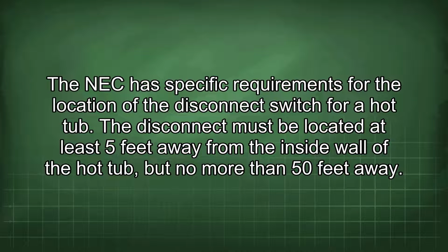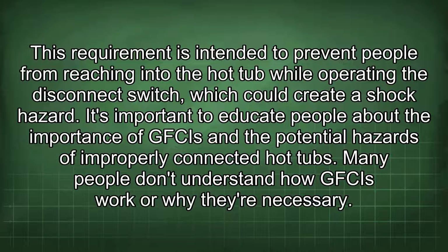The NEC has specific requirements for the location of the disconnect switch for a hot tub. The disconnect must be located at least 5 feet away from the inside wall of the hot tub, but no more than 50 feet away. This requirement is intended to prevent people from reaching into the hot tub while operating the disconnect switch, which could create a shock hazard.